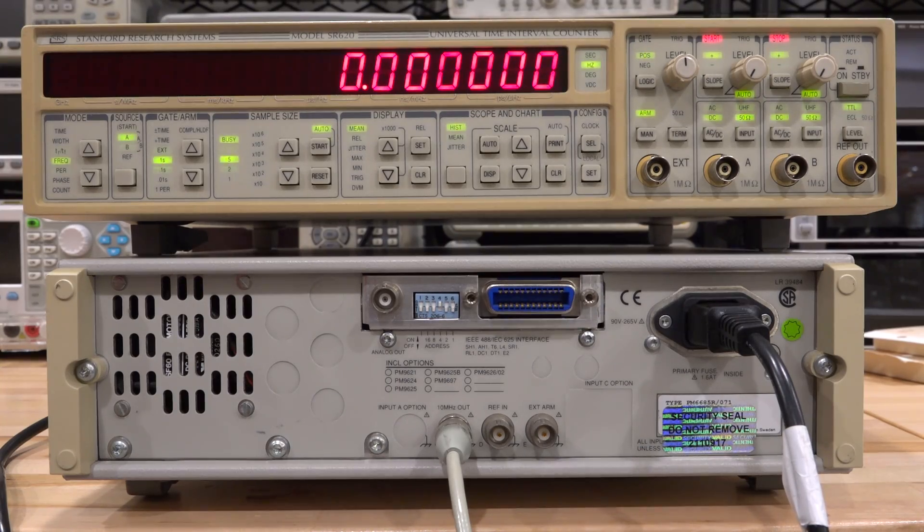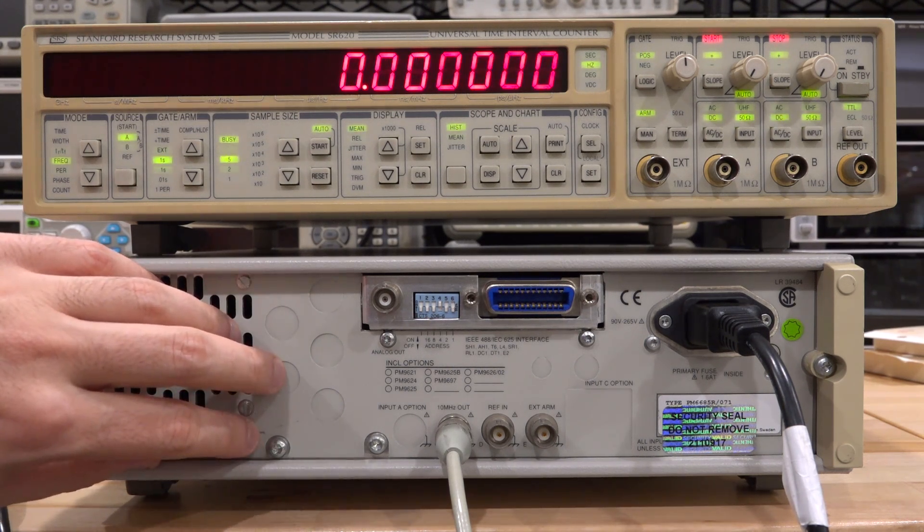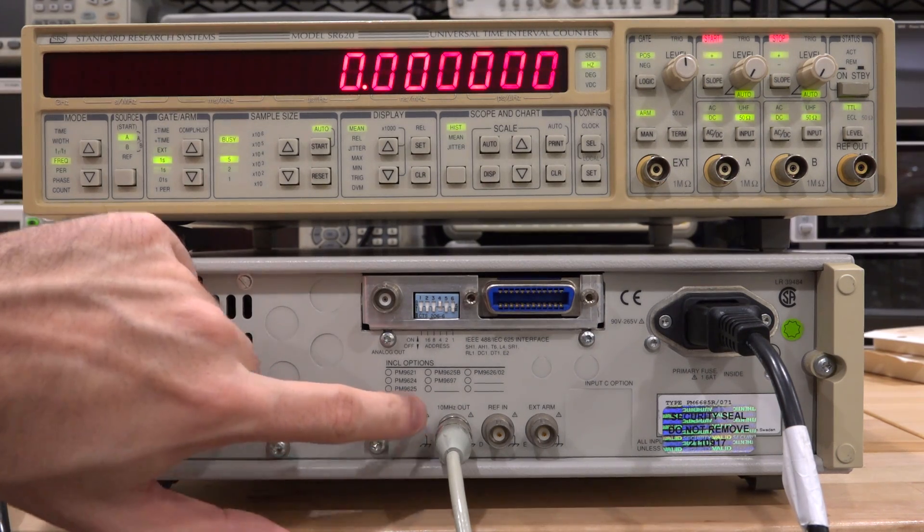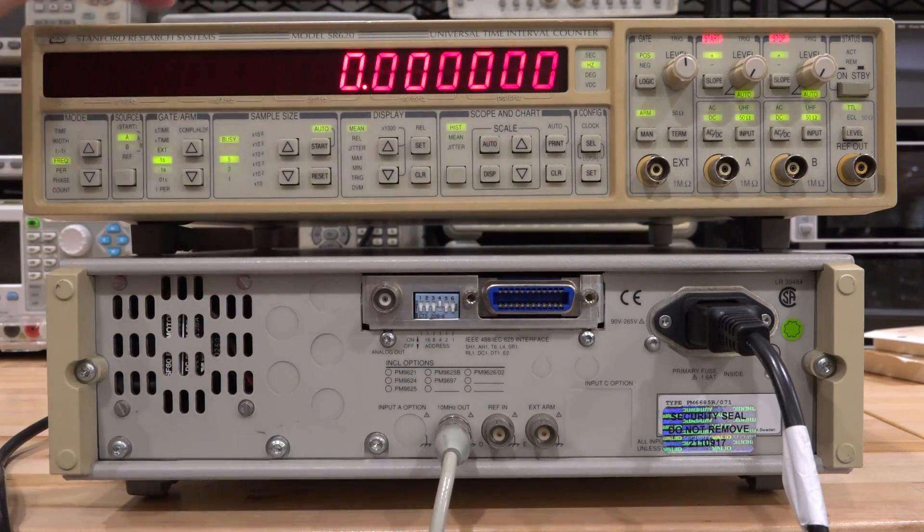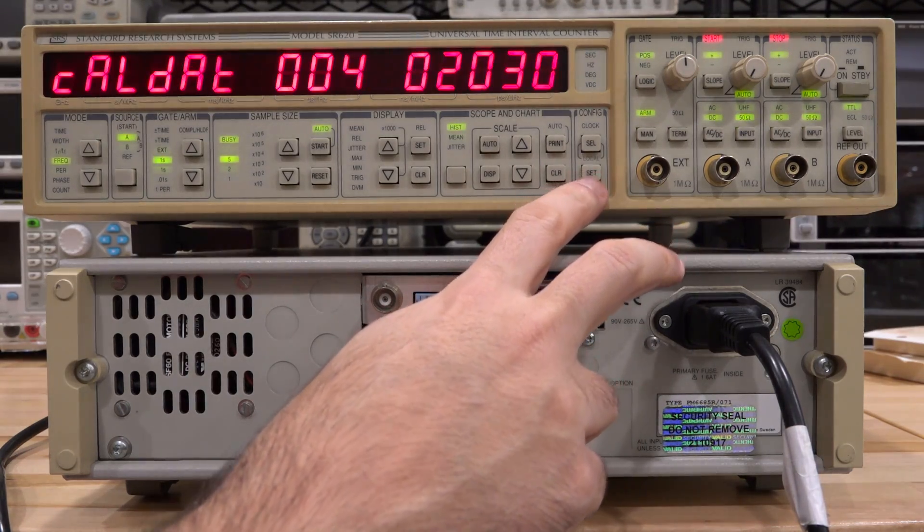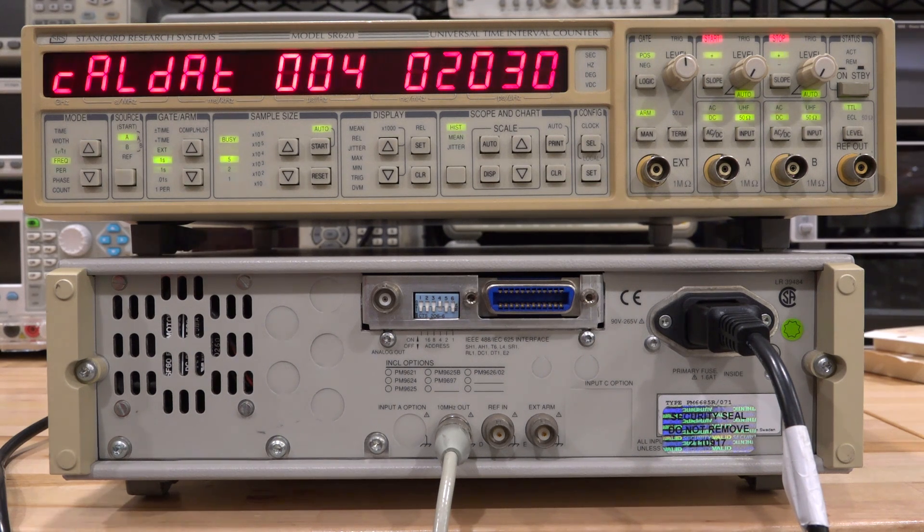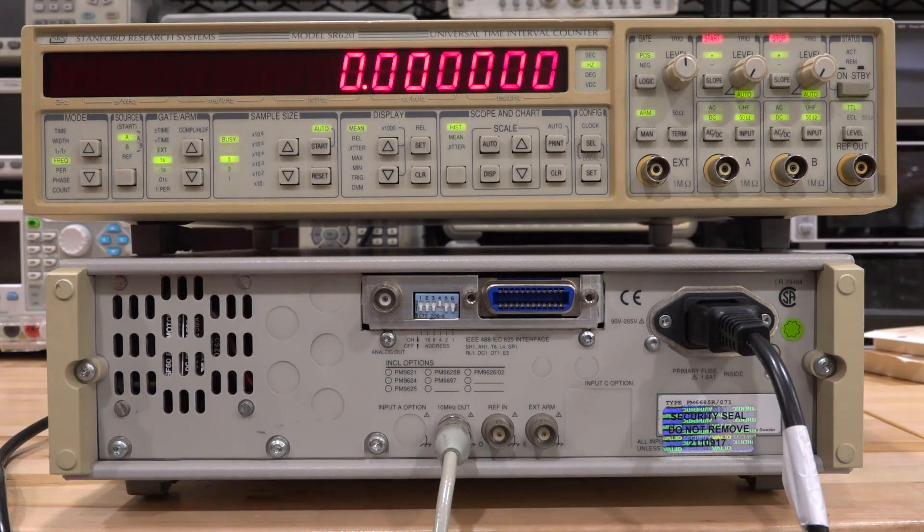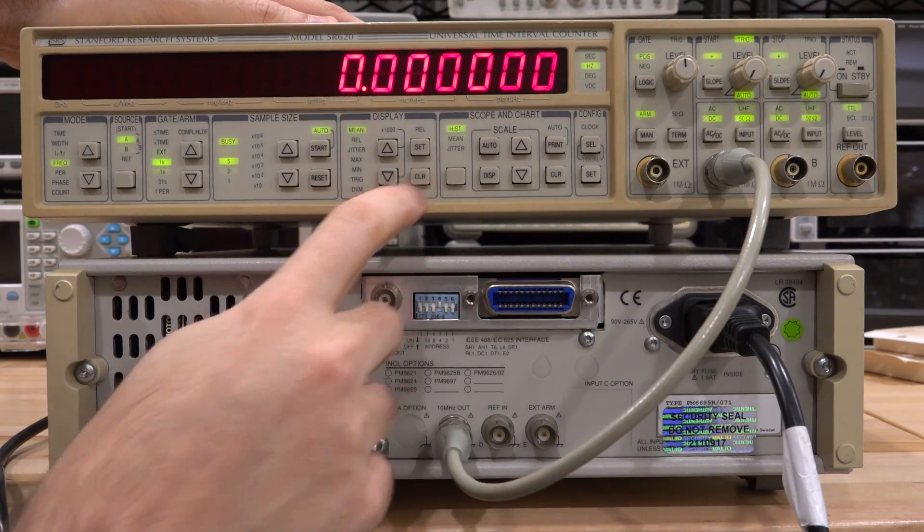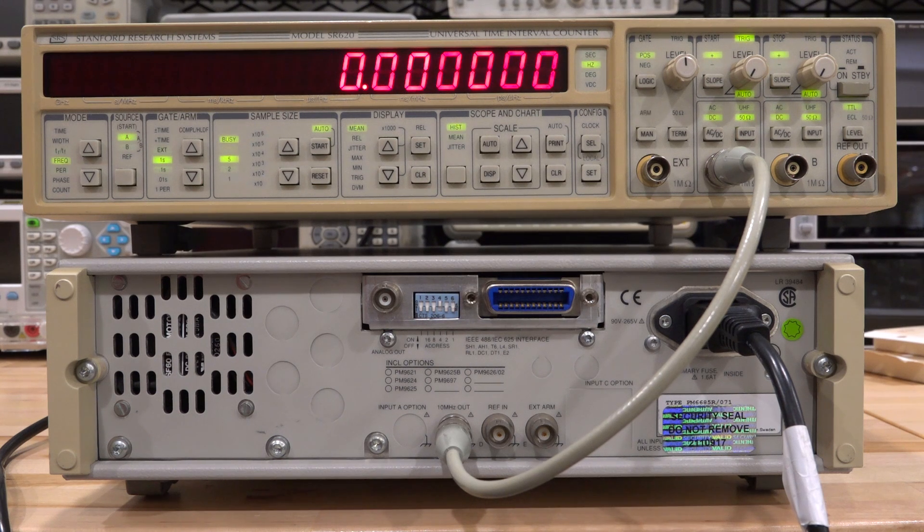Let's take a look at the frequency accuracy of the SR620. At the bottom I have a rubidium source, this is a frequency counter with a rubidium reference built into it, and it puts out that reference also at the back of the instrument. That's why you're looking at the back of it. And I have this BNC right over here which we can plug into the front of this instrument. Now the SR620 also has built-in registers that you can adjust. So if you go through this menu, the register for this number here is the frequency trimming of the oscillator. It's actually a correction factor that you can enter in there. I fiddled around a little bit with it. Both of these units, both the rubidium as well as the SR620, have been on for a couple of hours to really stabilize them, make sure they are basically where they settle at. So we can plug this in and see what we get.